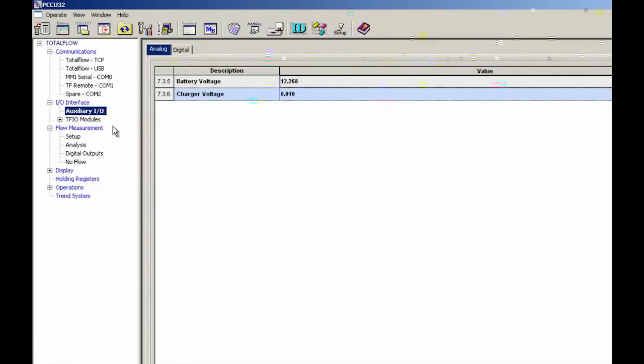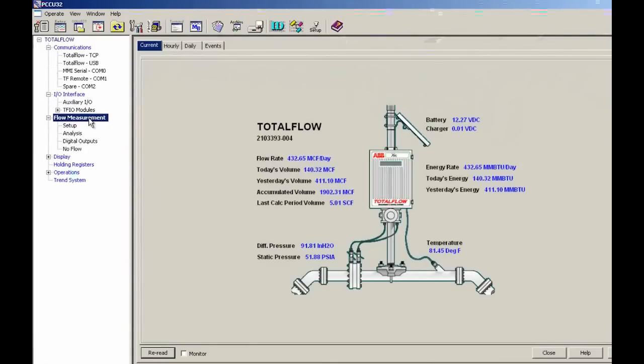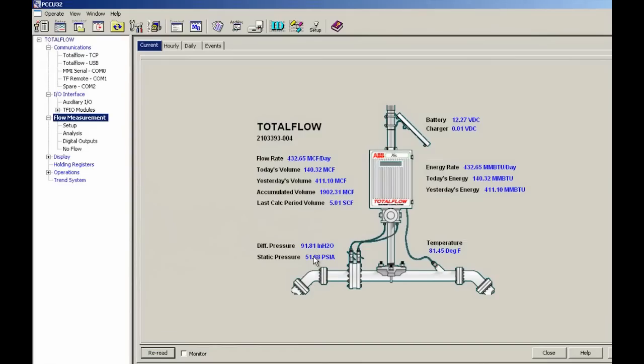And then the other points that we were going to trend, I'm going to drop down to flow measurement. One of those was flow rates. I'm going to hover over the flow rate and it's 11.7.19. We're also going to trend our differential pressure which is 11.7.0, static pressure 11.3.0, and temperature 11.3.3.